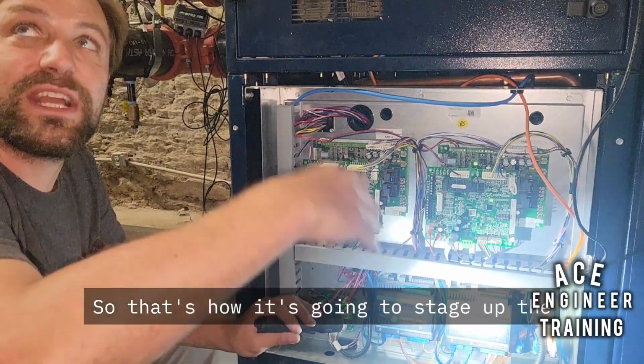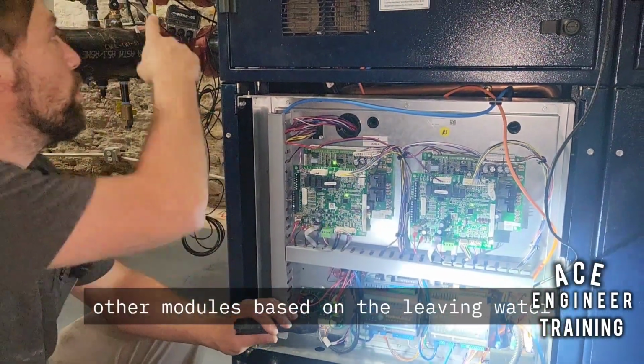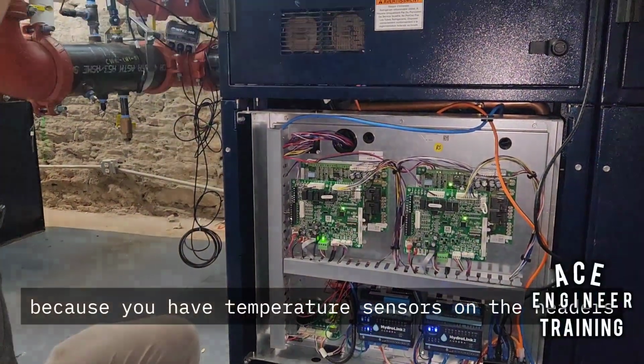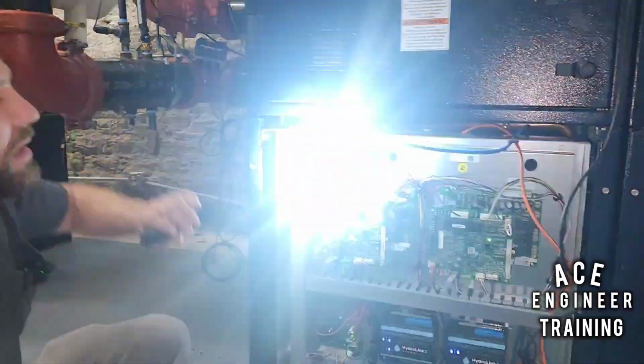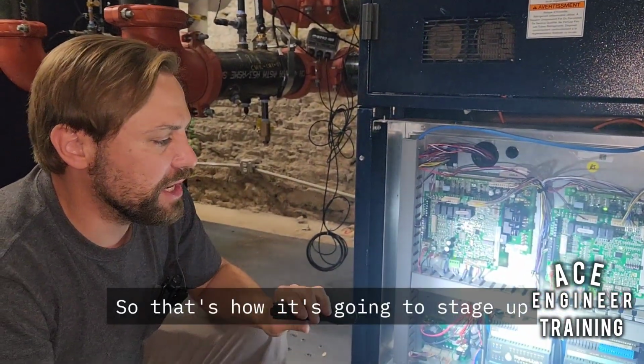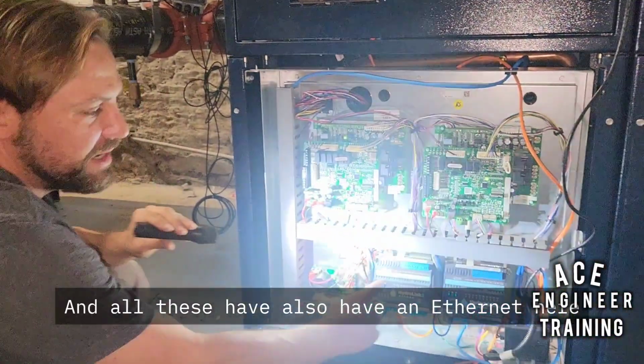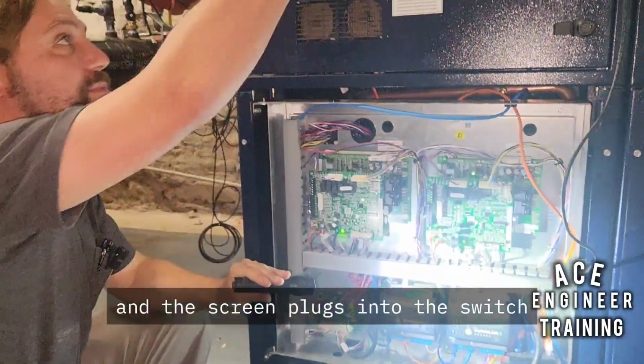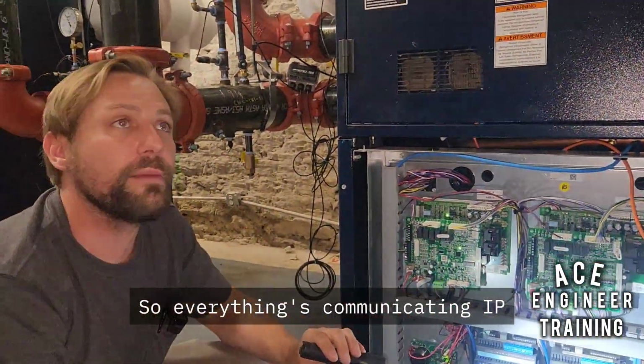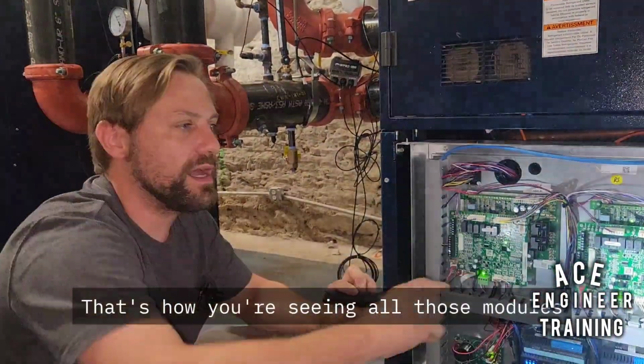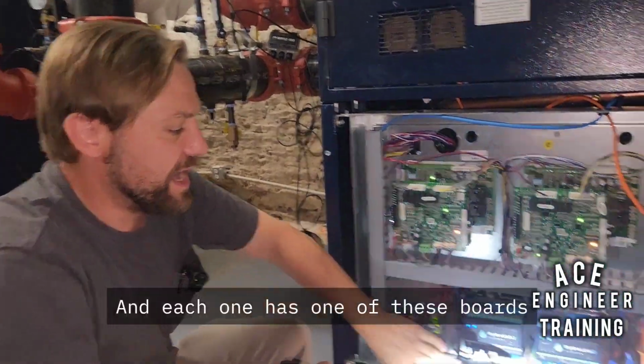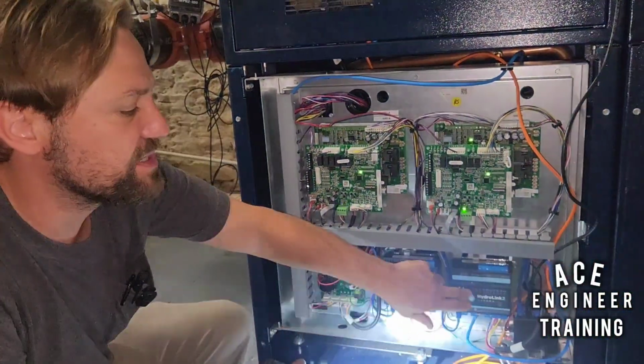That's how it's going to stage up the other modules based on the leaving water, because you have temperature sensors on the headers. That's how it's going to stage up. All these also have an Ethernet port, and they all plug into the switch, and the screen plugs into the switch, so everything's communicating over IP. That's how you're seeing all those modules - each one has one of these boards. This is the only one that's going to have 2.